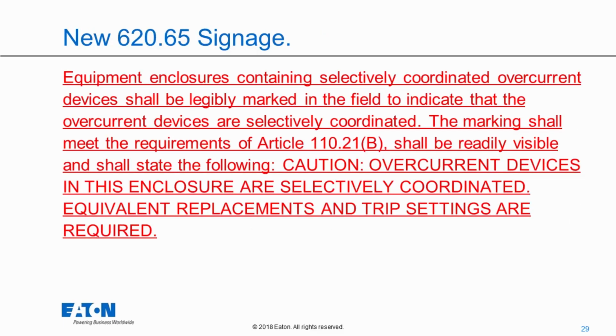Codemaking Panel 12 also went beyond what other codemaking panels have done, and they want to identify the enclosures by marking that we have selectively coordinated overcurrent devices in the field. So they require a field marking such as "Caution: overcurrent devices in this enclosure are selectively coordinated, equivalent replacements and trip settings are required." So now be aware it says enclosures, right?